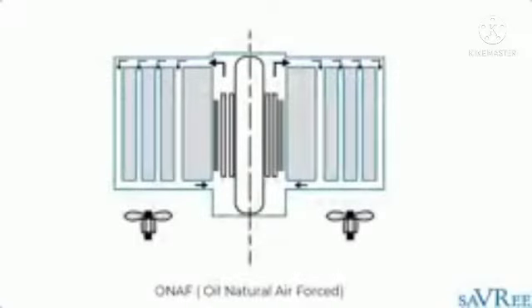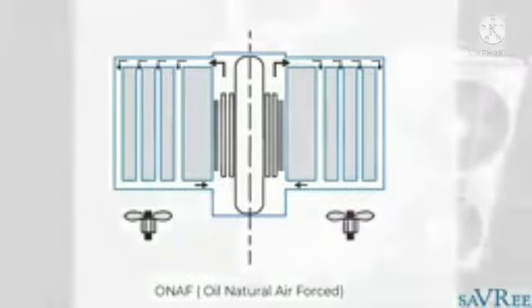The second type of cooling that is described would be the cooling associated with the insulating liquid itself. In our case, we have a natural convection process. So this transformer is an oil natural air forced type transformer, or ONAF as it will be written on the nameplate.